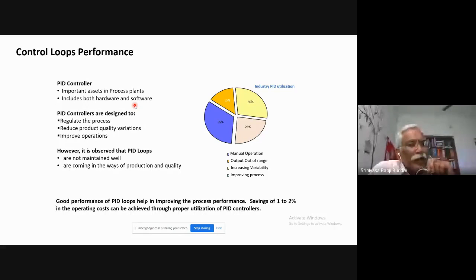Okay. Now the PID controls are primarily designed to regulate the process. When I say regulate, its job is to keep the process variables at the desired set points. There could be some disturbances because of load changes. There may be changes in the feed flow rate, or there may be changes in the feed quality. Even though such disturbances are taking place, the job of the PID controller is to keep the process value close to the set point.